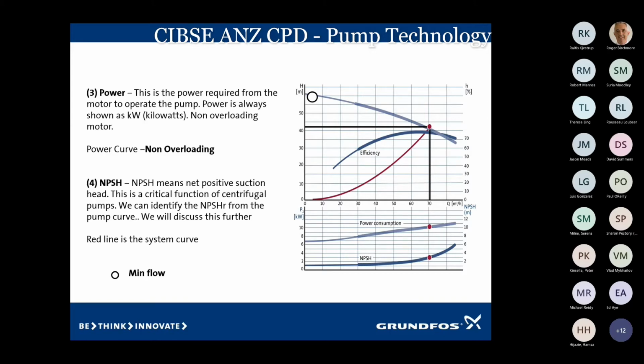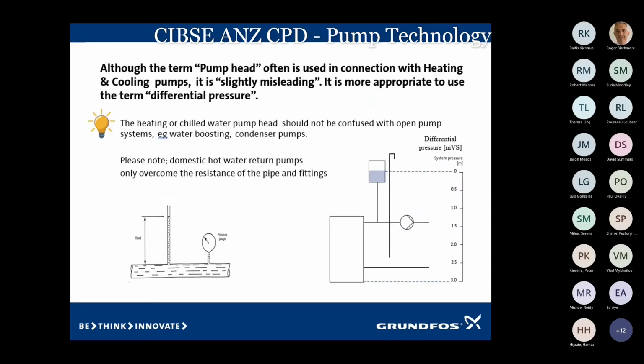they would be indicated with kilowatt ratings. So the left-hand side of the pump curve, it might have had a 7.5 kilowatt, then a little further down the curve, it might have had another 11 kilowatt, 15, and then 18.5 at the end of the curve. And that meant that wherever you sat that pump on that curve, that was the motor that you needed. These days, we have one motor fitting that whole entire pump curve, and then you shouldn't overload. I put this in. This is really quite good.